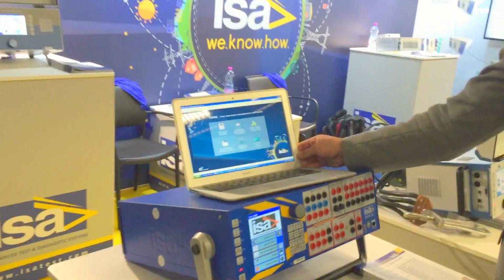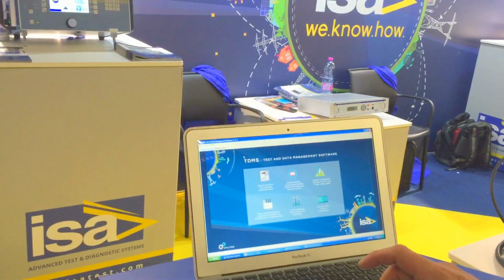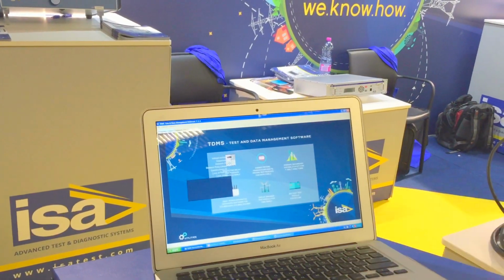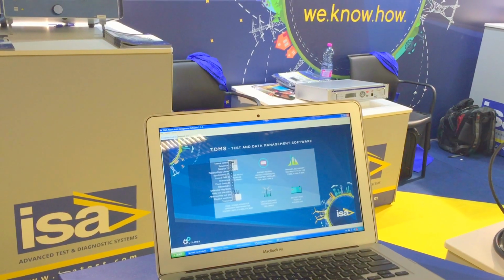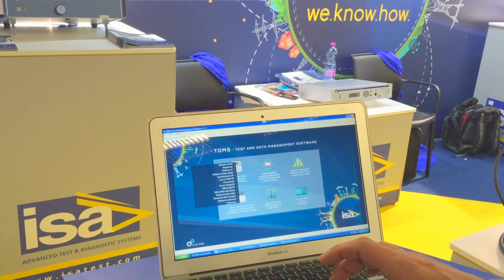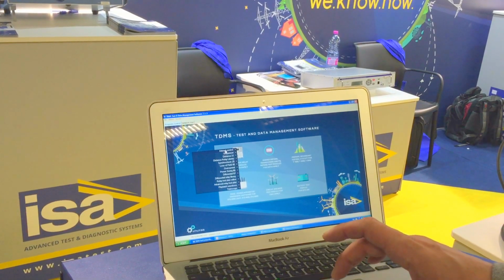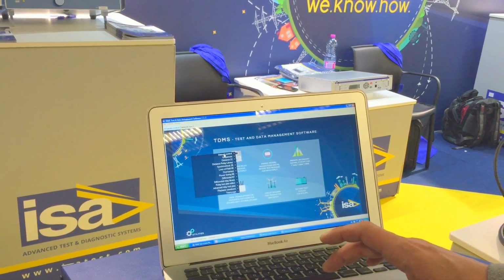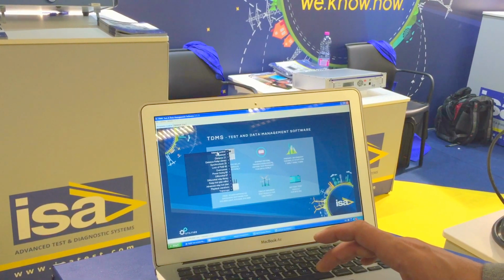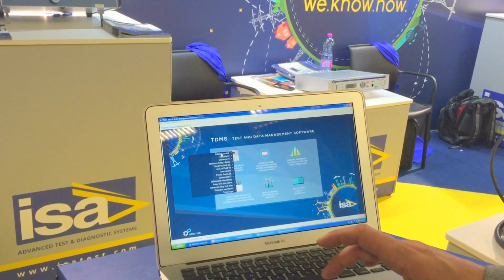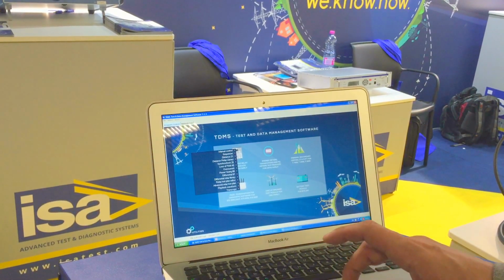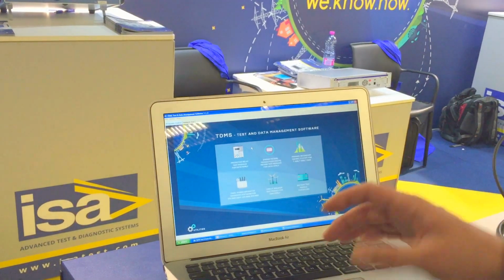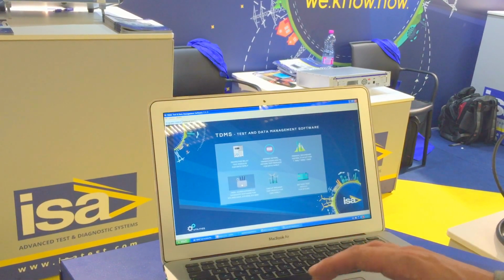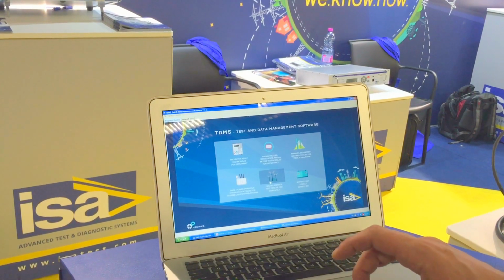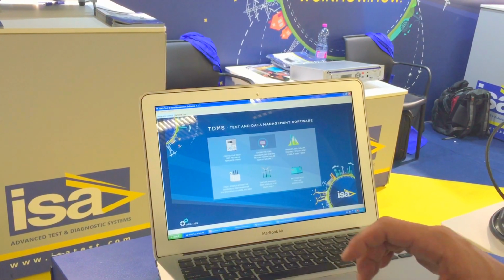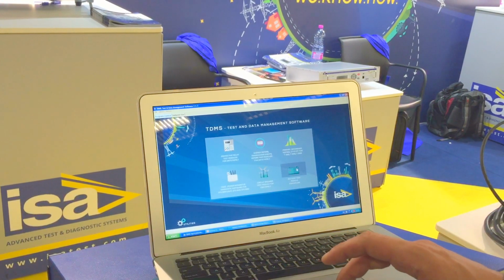This is the TDMS, our software. TDMS is complementary software, you don't have to pay for it, neither for any of the updates. And with the software you get manual control, sequencer, distance protection, synchro check, loss of field, overcurrent, power swing, differential protection, and a huge library of distance and differential relays. TDMS also allows you to test transformers using another application, circuit breakers, and also energy meters, transducers, and power quality meters, and you can also test batteries.